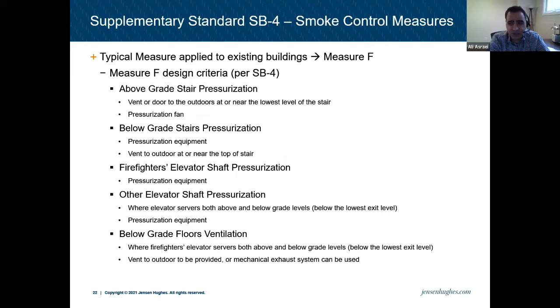Usually when you see measure F, you can see a sprinkler in the basement parking area and that's it, or the garbage chute and stuff like that. But then the actual floor areas, they're not sprinklered. So it is asking for above grade stair pressurization. When you're pressurizing the stair from above grade, you need to have the ventilation, the vent at the bottom of it, which is typically the door that opens. If you need more than a door, then for certain numbers of stories you end up with a certain size of opening that you need. The door is not enough.